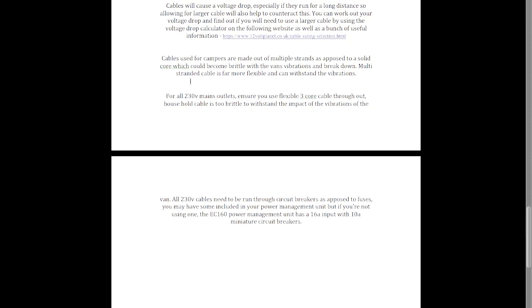For your 230 volt mains outlets, ensure you have flexible 3-core cable throughout. 3-core means it will have 3 different cables: your earth, your neutral and your live. The household cable you would normally use is too brittle and won't withstand the impact of the vibration, so again make sure it's flexible cable.